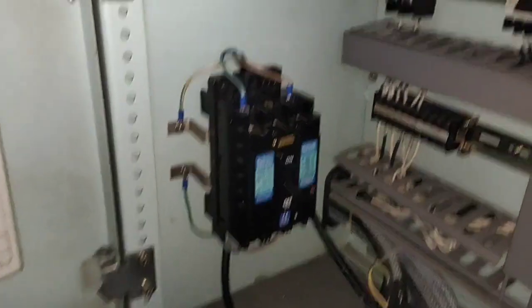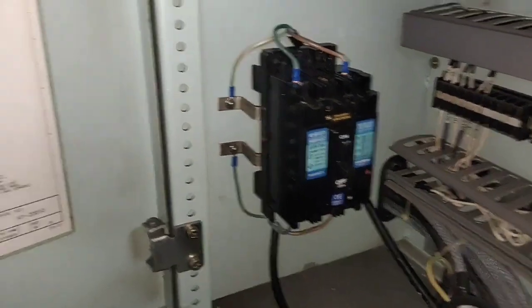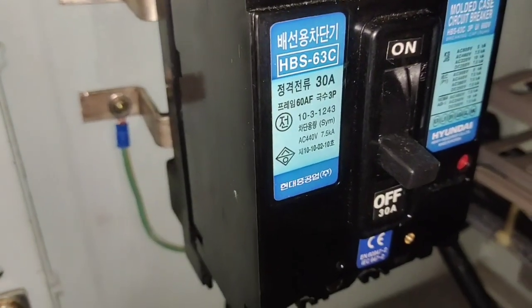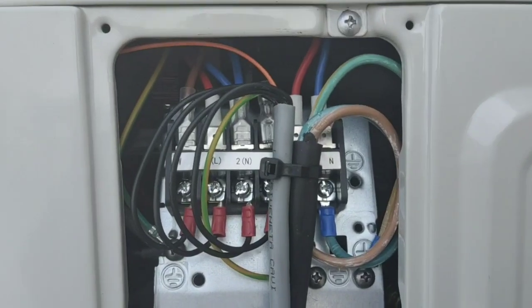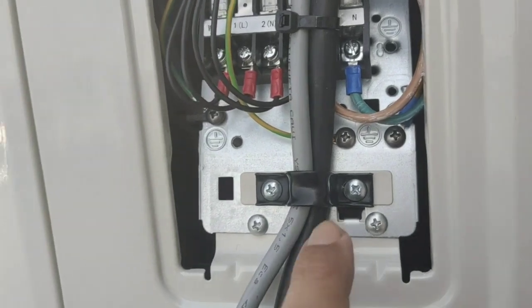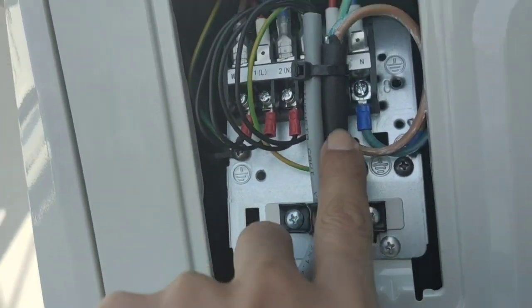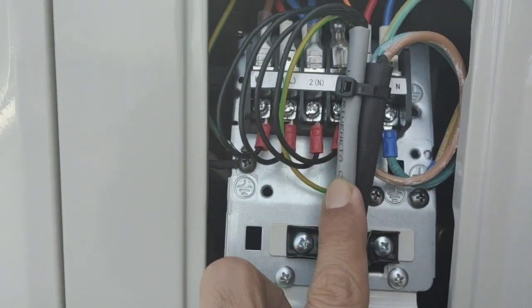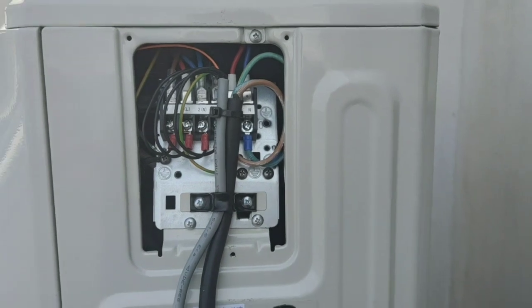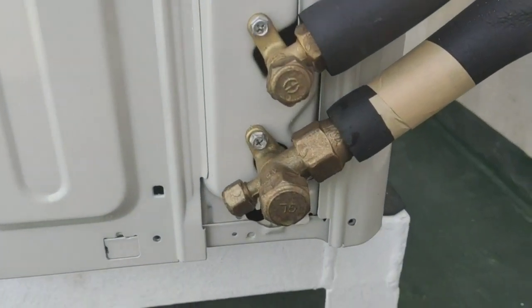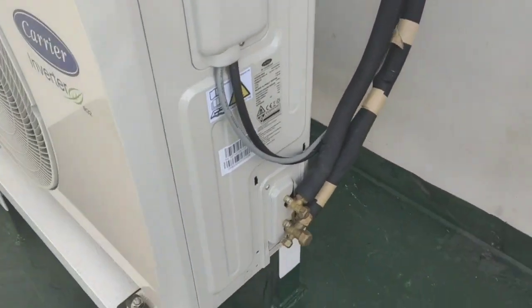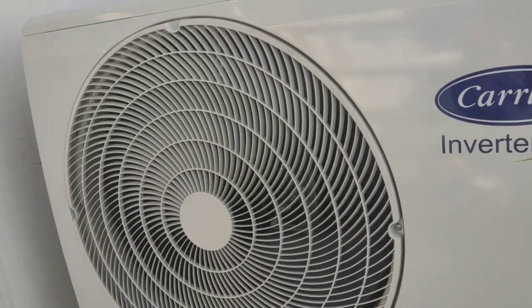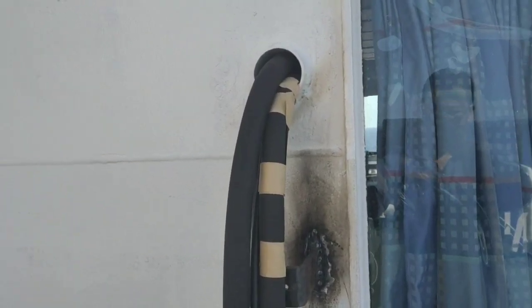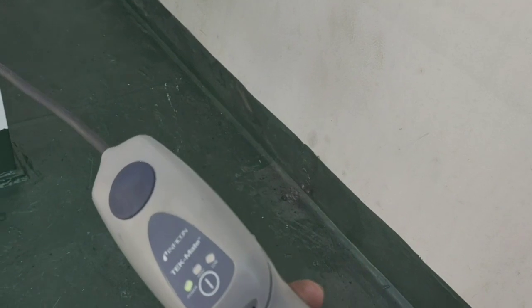Now this is for the power supply. I'm preparing this circuit breaker to be the power supply of the compressor. This is a 30 amperes circuit breaker, and here is the connection of the condenser side. This is the power supply coming from the circuit breaker, the black one, and this gray one is going to be connected to the evaporator side. It serves as the power supply of the evaporator also to run its fan. And here we have finished the installation of the compressor and condenser side, and we have also insulated the pipes.